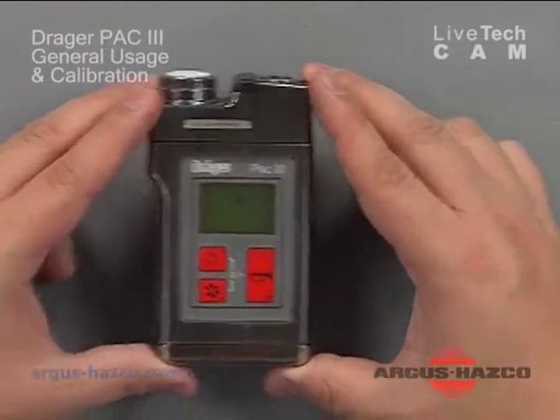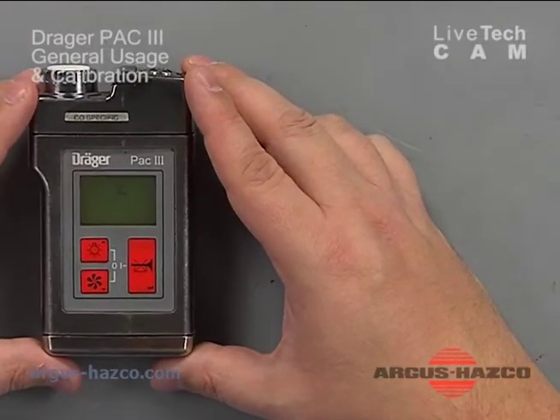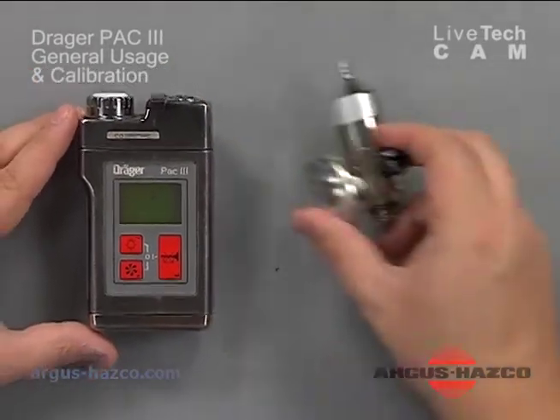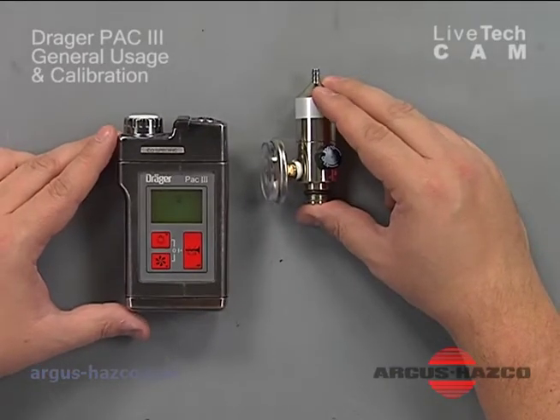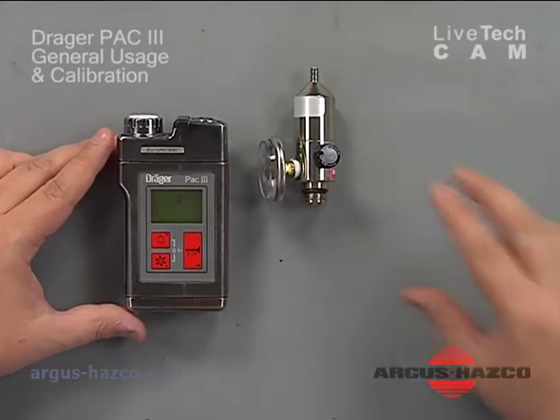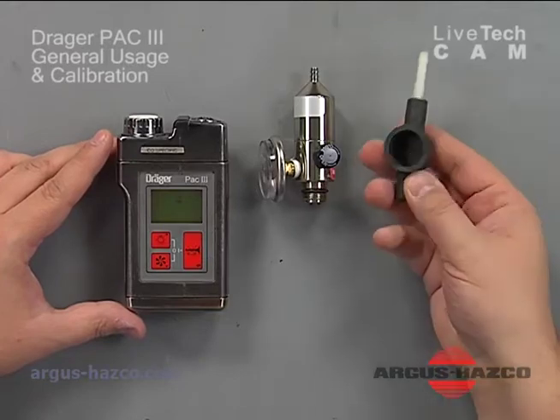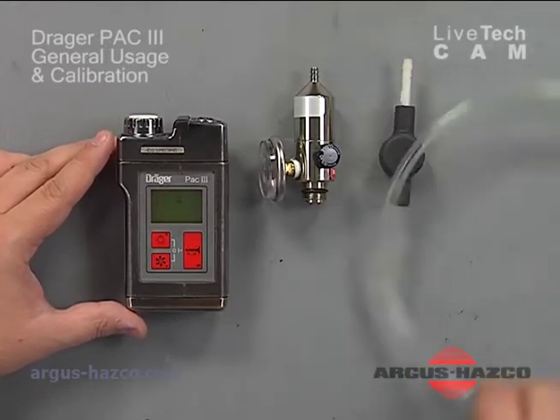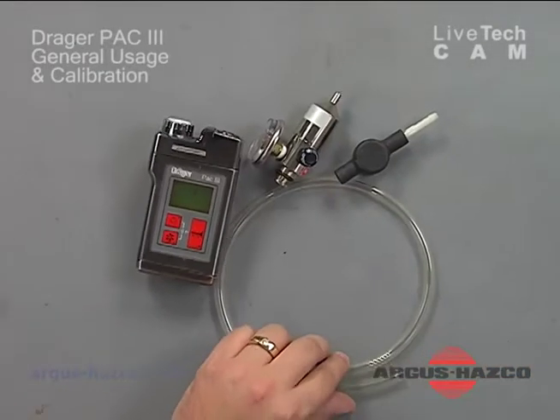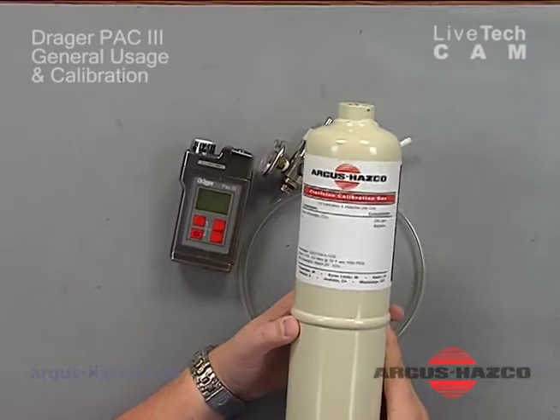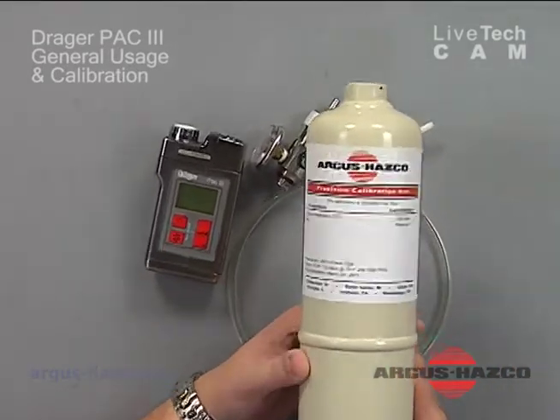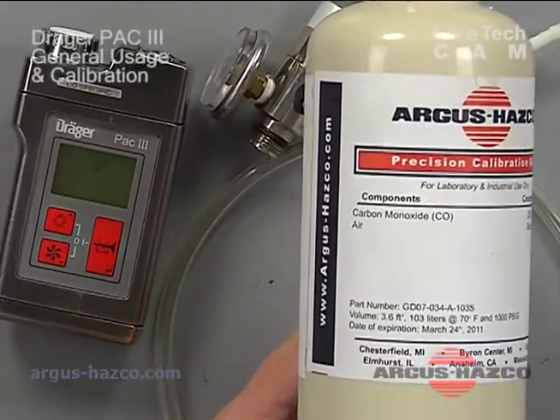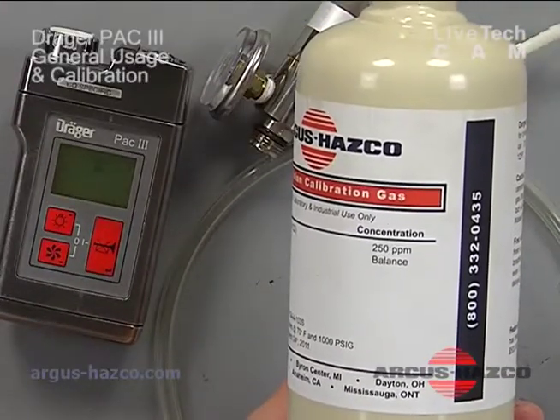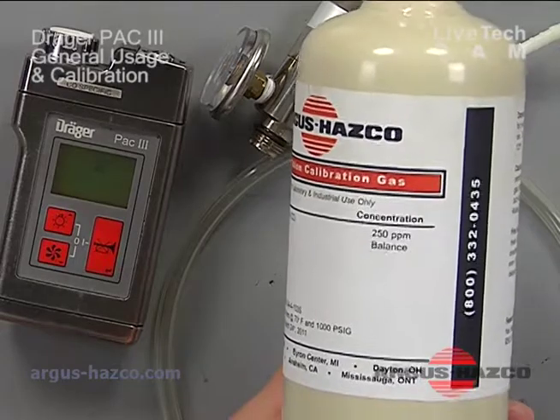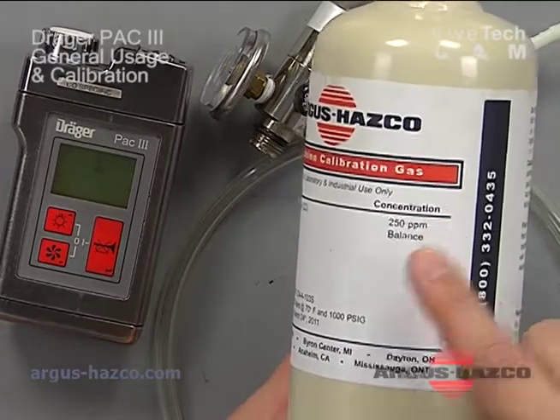For a calibration, you'll need your Draeger PAC III, if you can zoom out a little. About a half a liter to 1 liter per minute regulator, set flow rate. Your calibration adapter, a piece of tubing, and then your calibration gas cylinder. If you can zoom back in, you'll see it is carbon monoxide. This is set at 250 ppm. You want to ensure that your calibration value on your cylinder matches that you configure on your instrument.